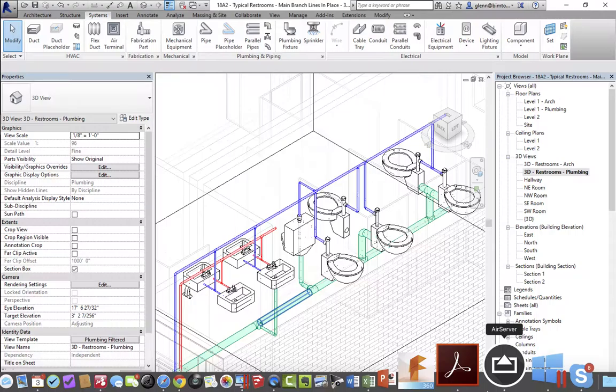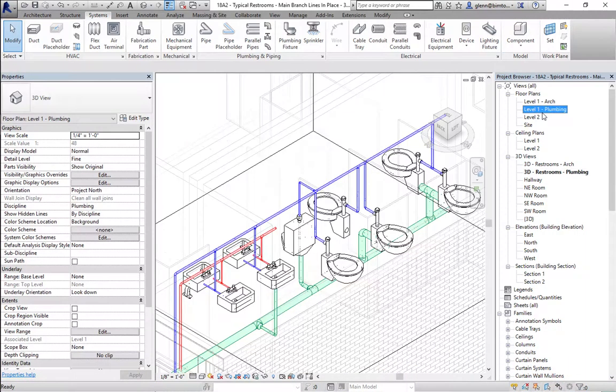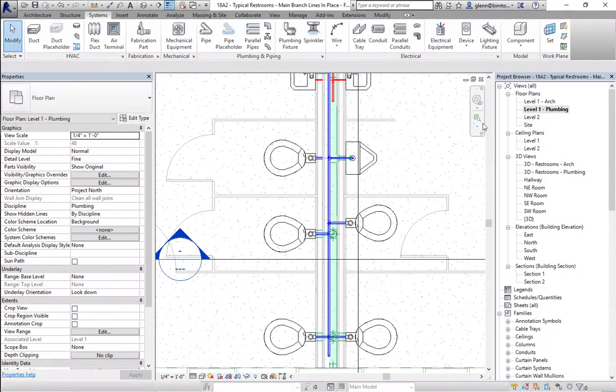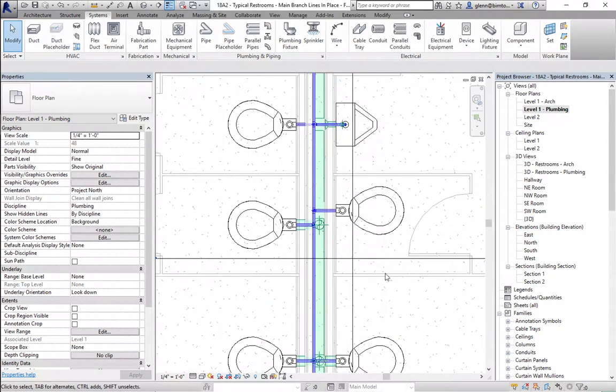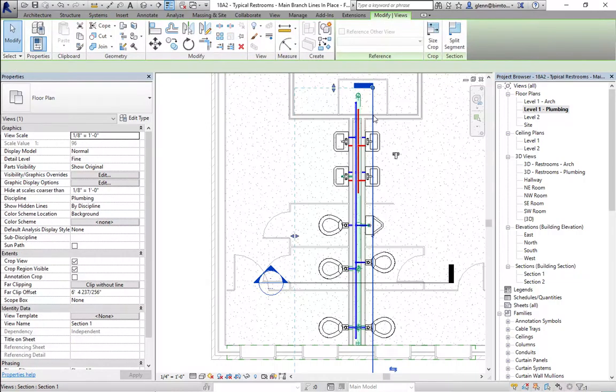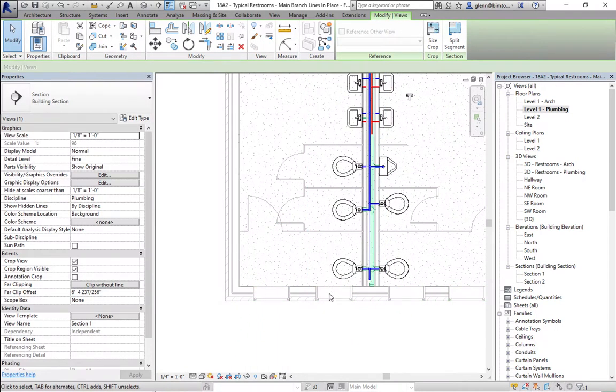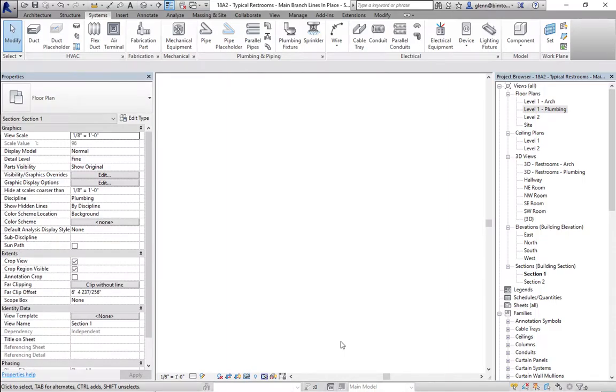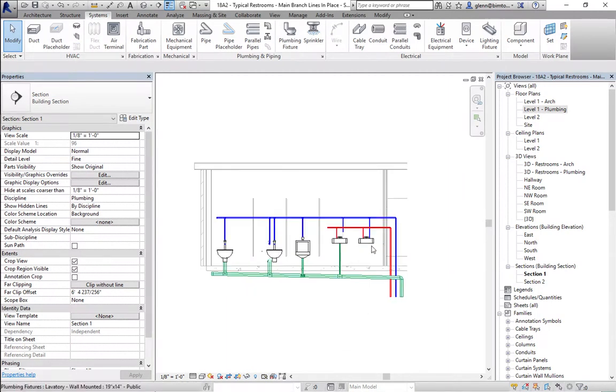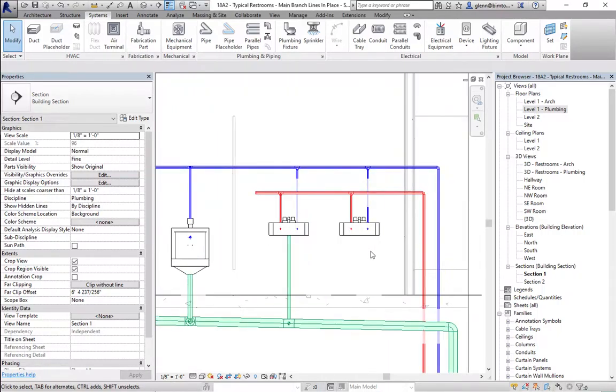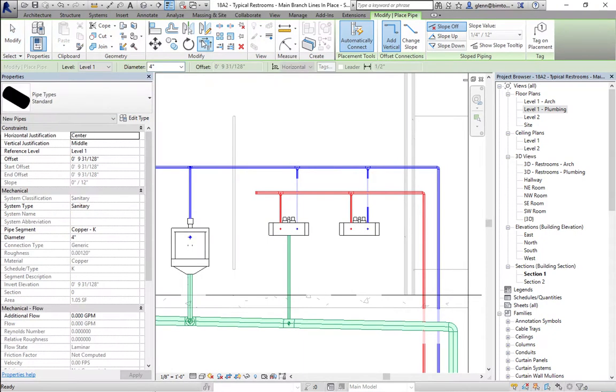The same thing happens with sinks — connecting in causes it to drop straight down. The key is to outsmart it: tell it what you want by getting very close to the connection but not completing it, and then it'll connect into where you leave it. What I recommend is to come to the plan view, keep a section perpendicular to the pipes and one parallel to the pipes — that makes it a lot easier to connect, just like when we were connecting air handlers.